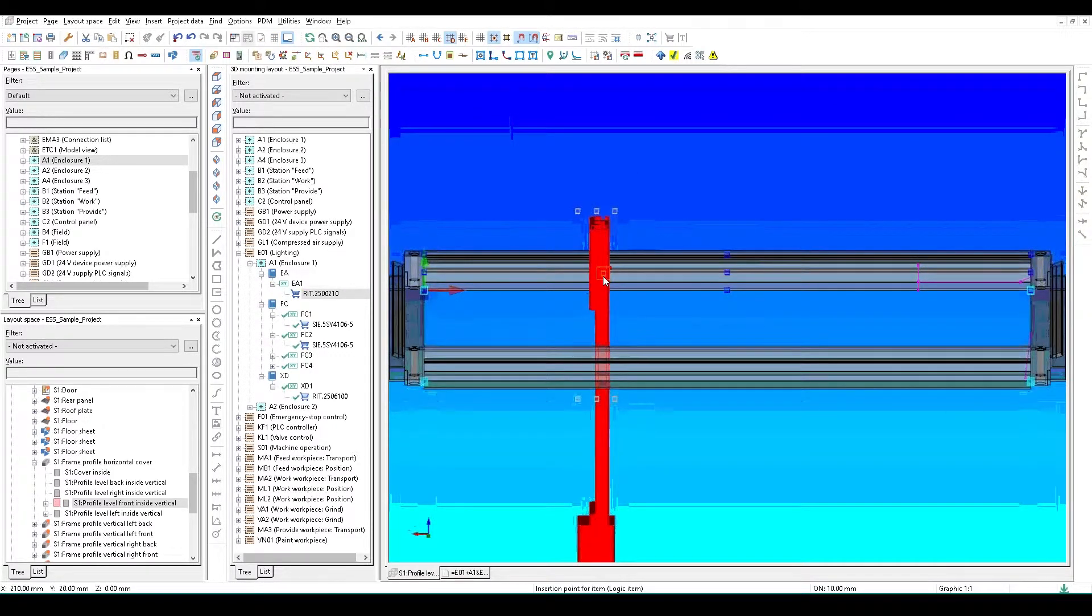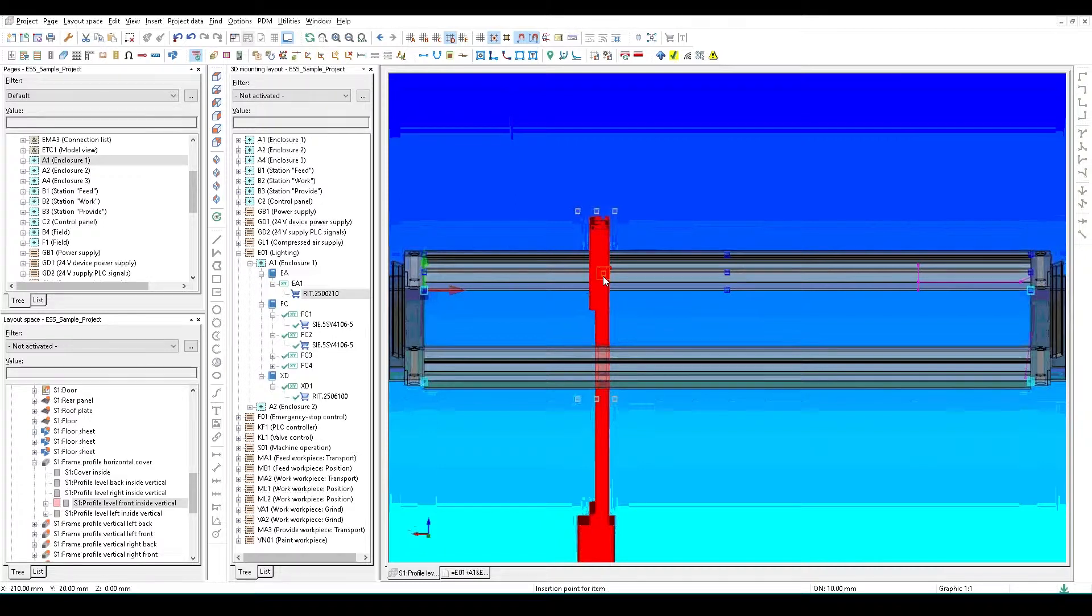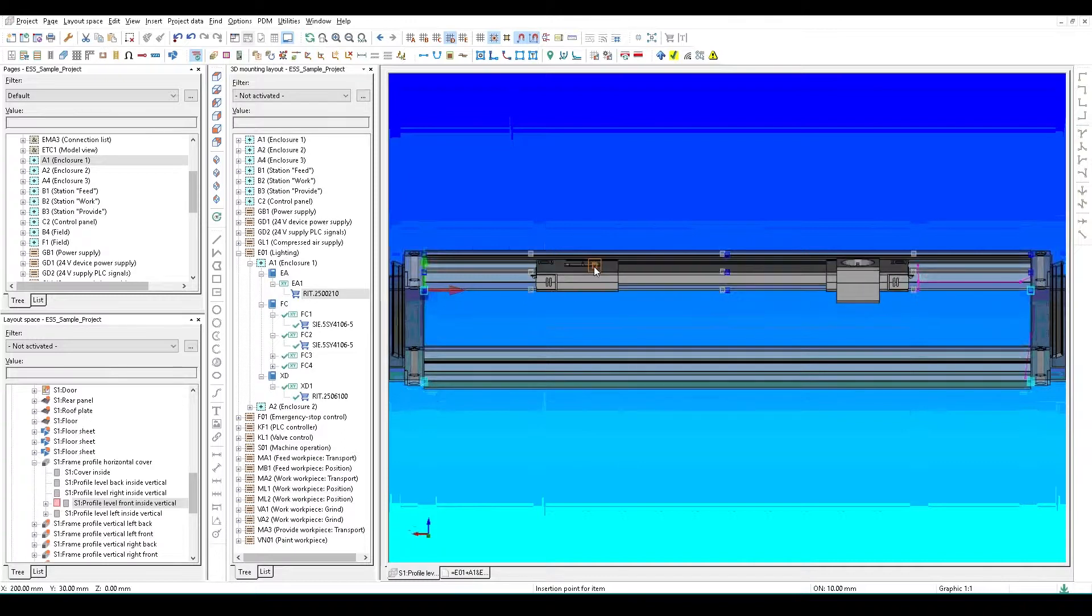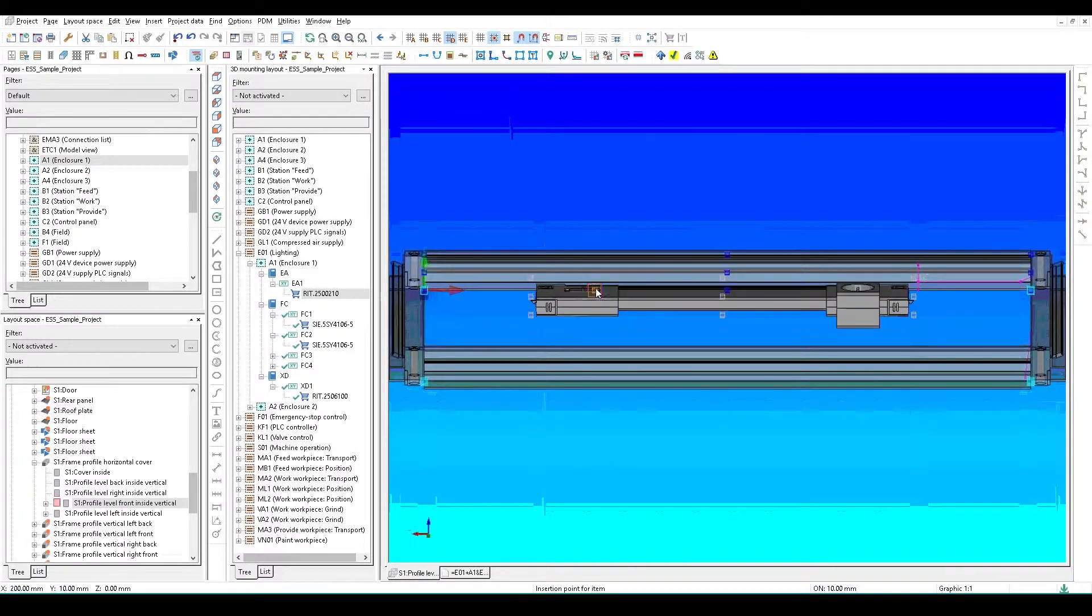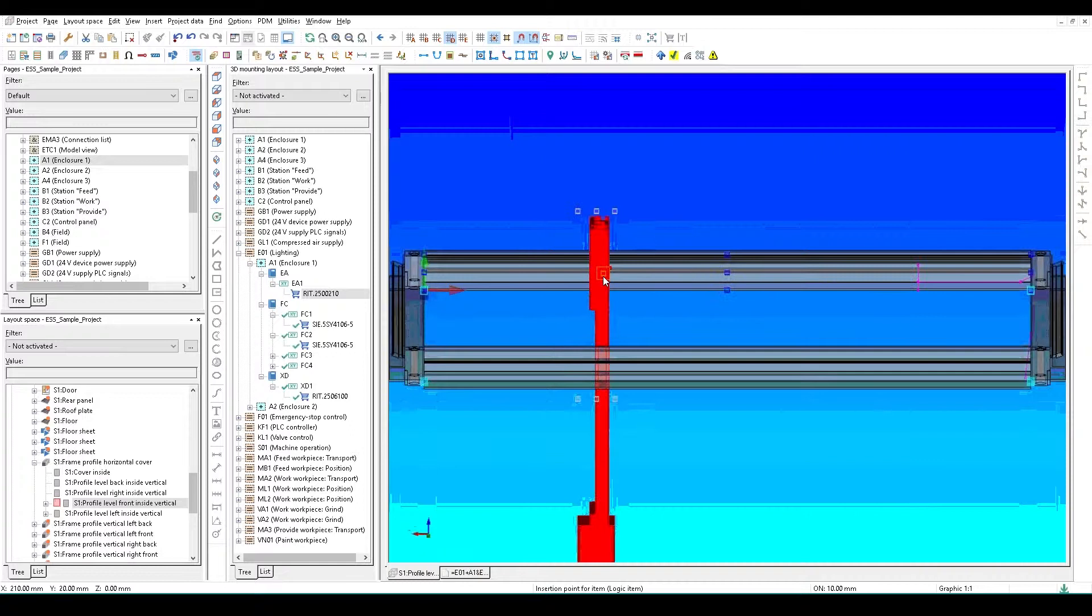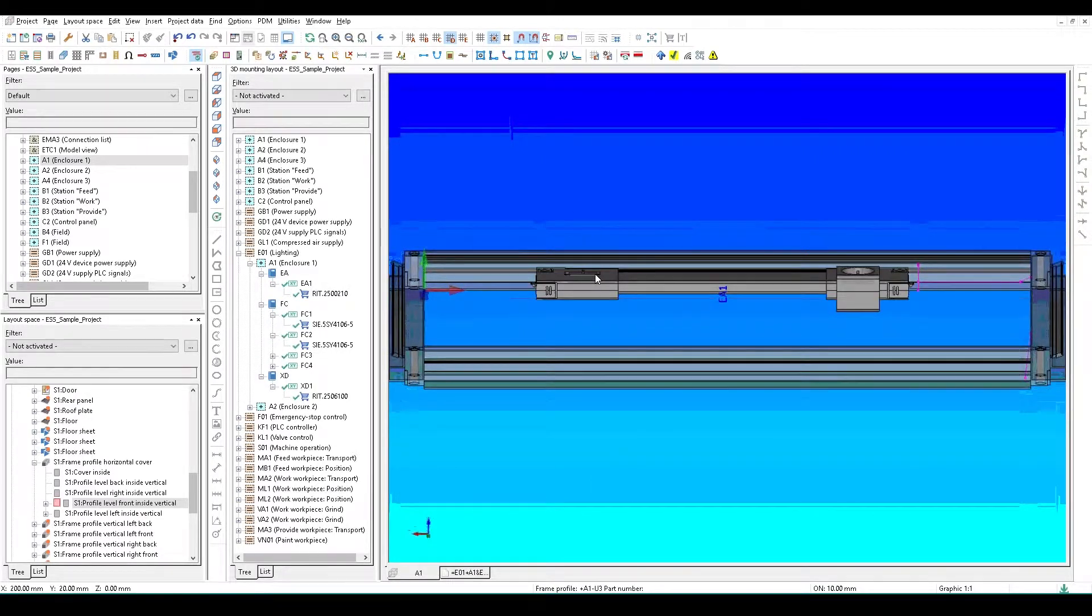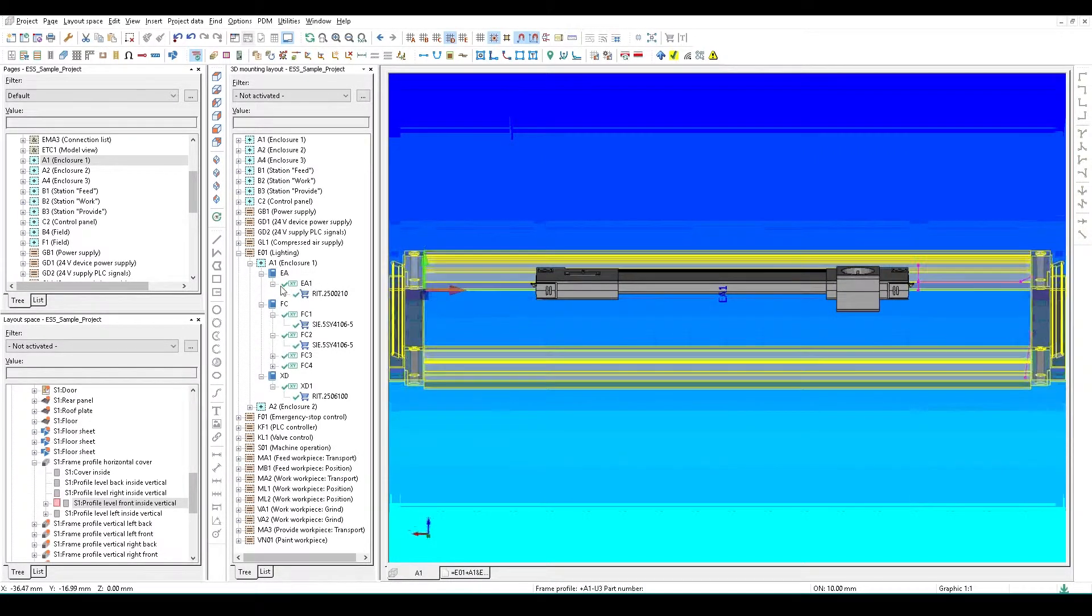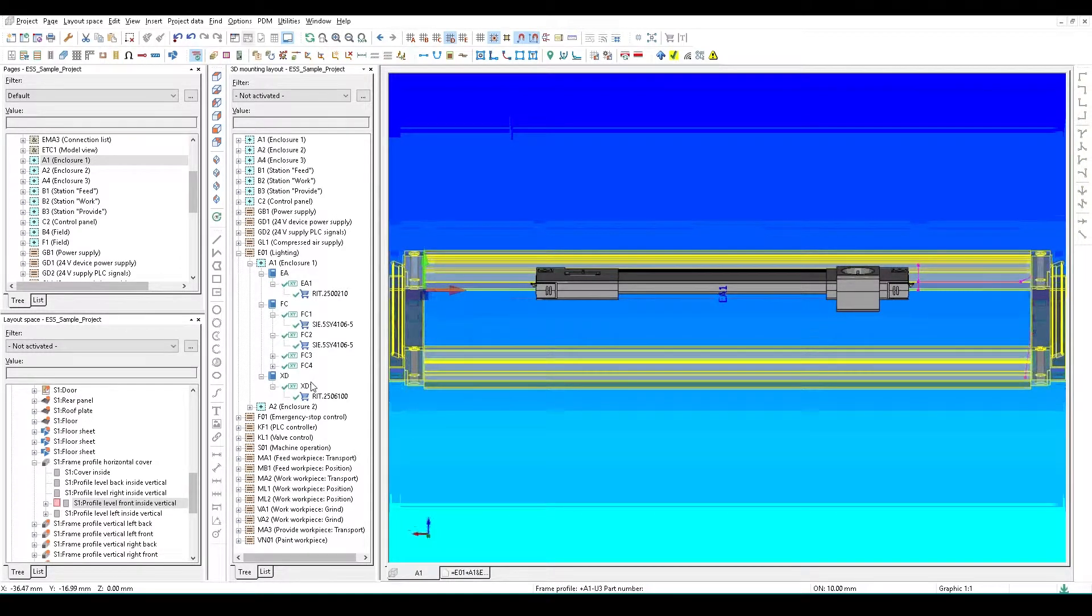Again, simply just click and drag it across. Ah, something's gone red. Why have you gone red? Well, I've got collision control on. So collision control is going to stop you from putting an item in the wrong place. Now, panel builders do have experience and knowledge. They're experts in getting the panels to fit, but this little bit of help is going to make sure that this light doesn't collide. It doesn't hit against the door, doesn't hit against the roof. It is going to fit onto an item in the right line. Press it onto the rotate section on here. When you see just a simple move, then obviously it stops me from putting it in the wrong place. Click it down, and now ePlan has sorted it all out for me, you can see. I've got my green tick. I know that schematically, everything is in place. I know the panel, everything is now in place, and my lighting system has now been placed down.